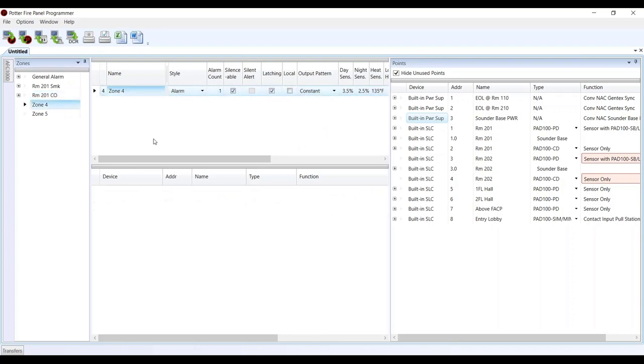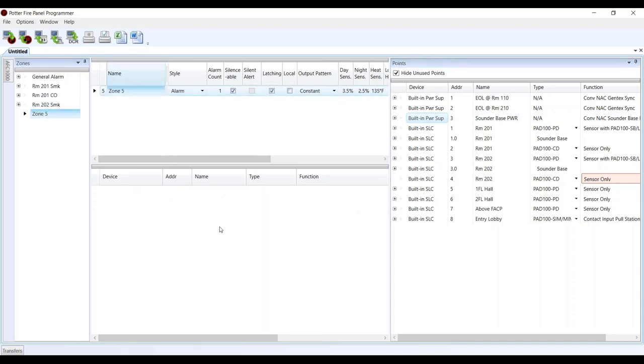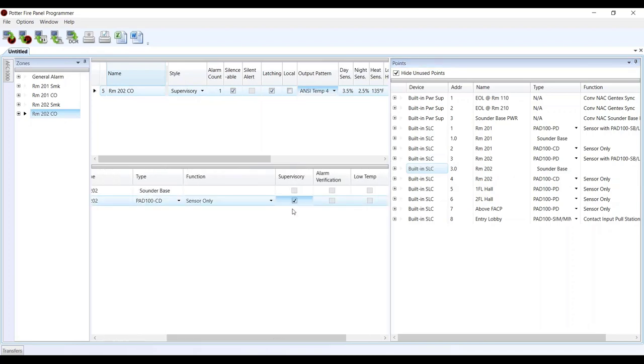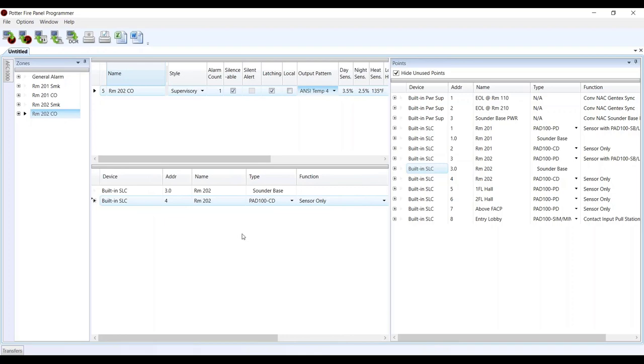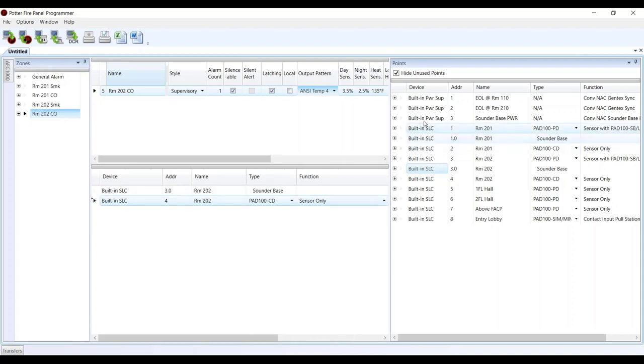Let's jump down to zone 4 and do room 202. Non-latching, same as 201 — temporal 3 for the smoke detector. Grab the smoke, the sounder base comes with it, then add in the sounder base power. Zone 5 is the CO detector — supervisory style, change the pattern to temporal 4. Put in the CO detector and the sounder base from the smoke detector. Make sure supervisory is checked on the CO detector itself — if you have an alarm point in a supervisory zone you'll get a red box. Then put in the sounder base power.